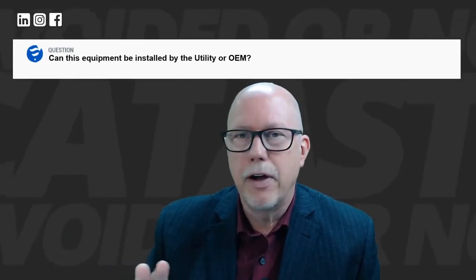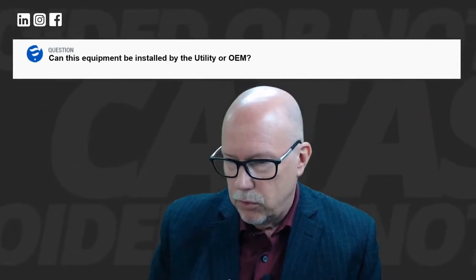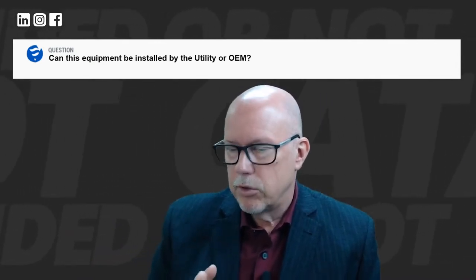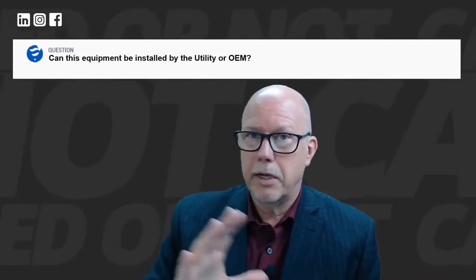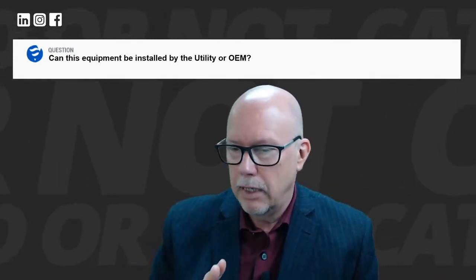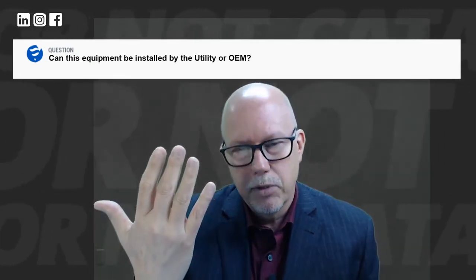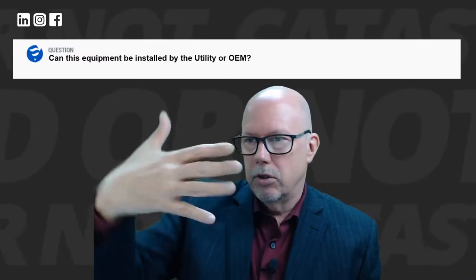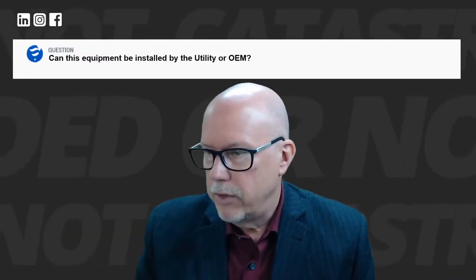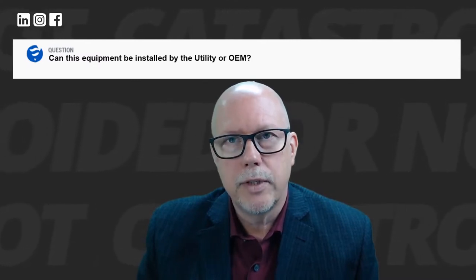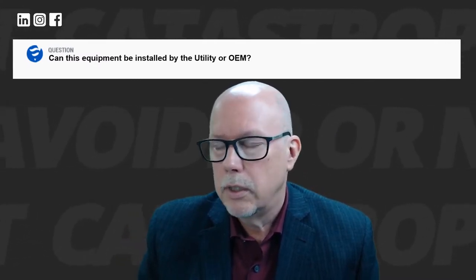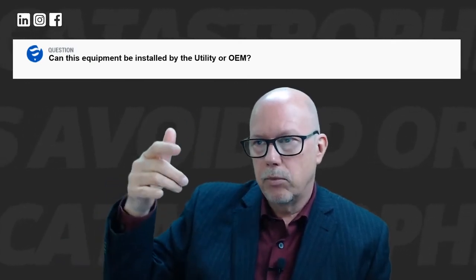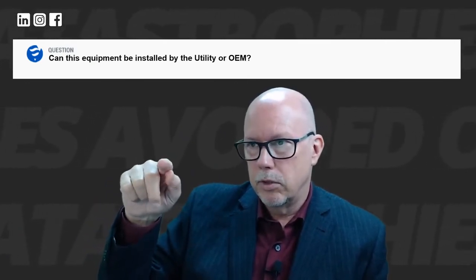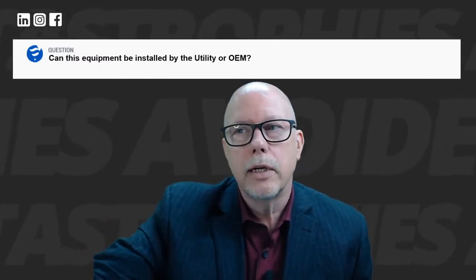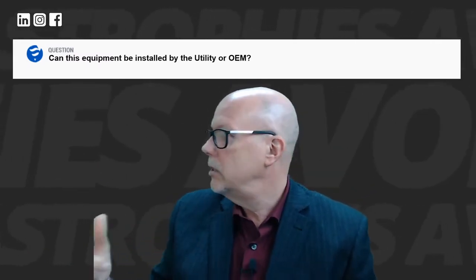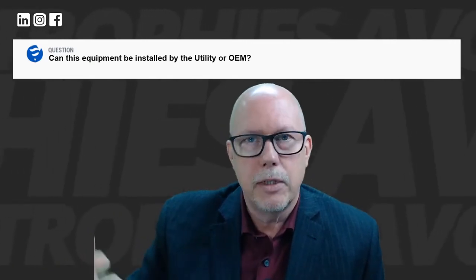In my 25-year career, I've learned our customers are very creative, they can come up with all kinds of incorrect installations. I've seen sensors installed on the opposite side, sensors installed sideways, and one case with a pole temperature probe where they installed two: usually you put one at the top and one at the bottom, but these guys installed one at 0 degrees and one at 180 degrees, looking at the same area, so the temperature readings were the same. Somebody didn't read the manual.